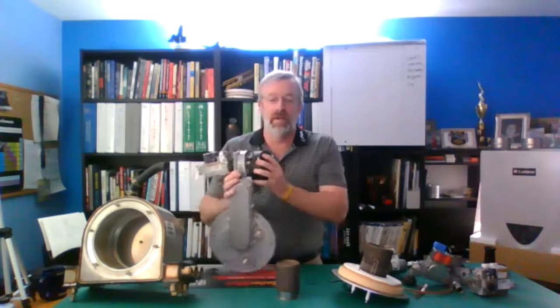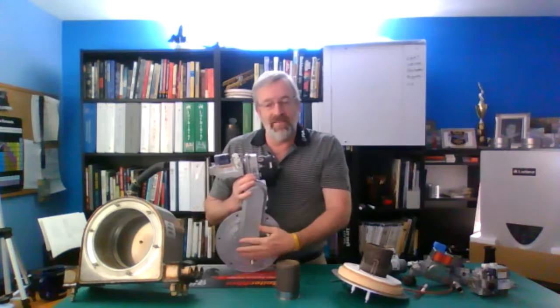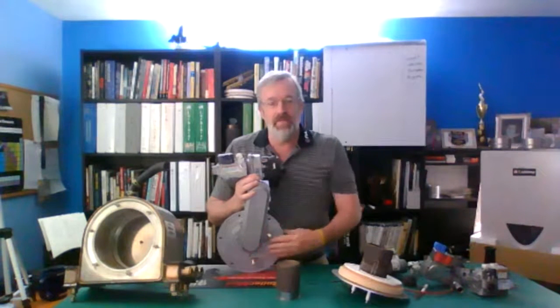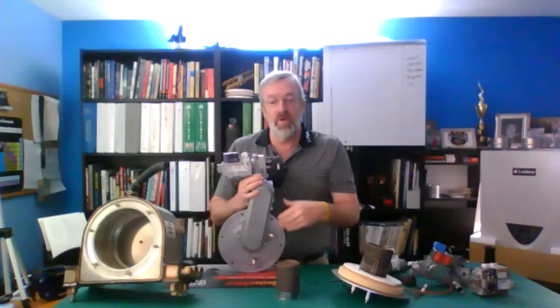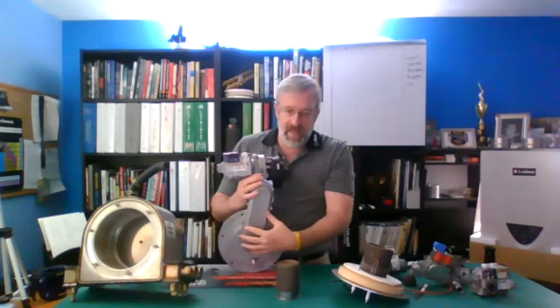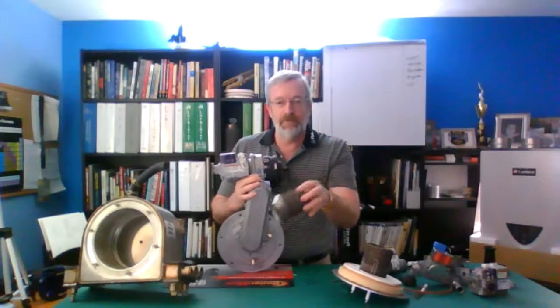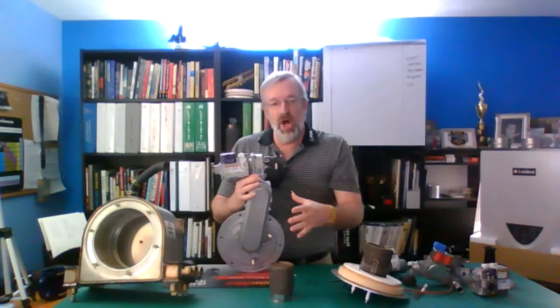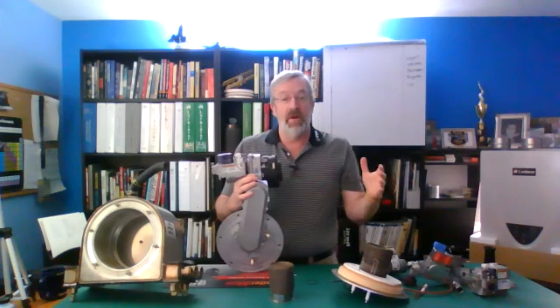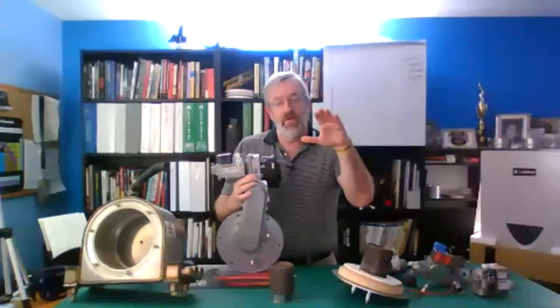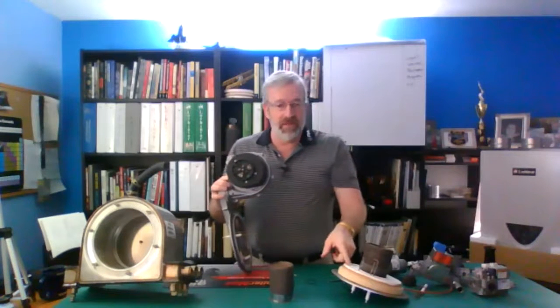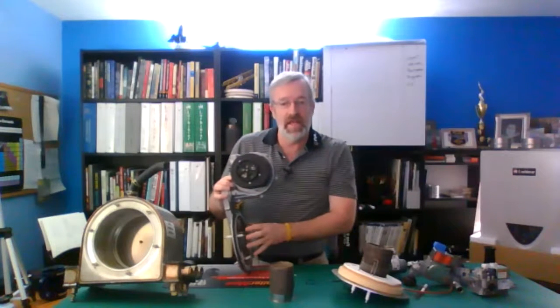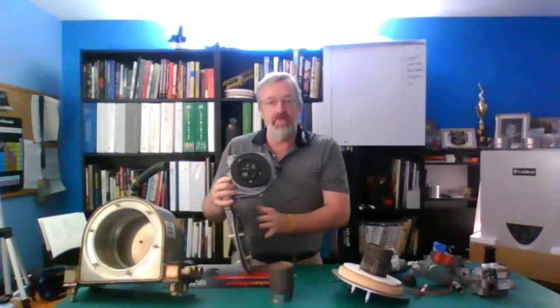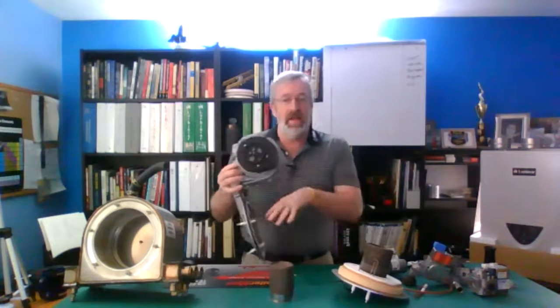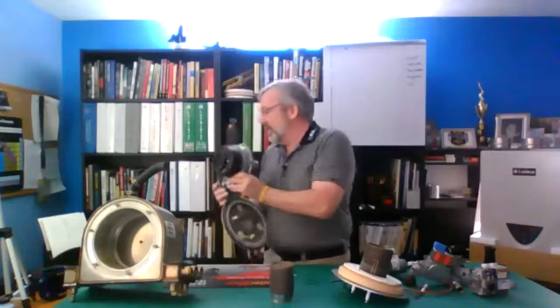Now, real important, don't take this off while this burner assembly, this front door, is still connected. If you take that off, now this is a short one, but when you're into some of the longer ones and you've got maybe a 24-inch burner, the weight of that burner will drop down and basically will crack the refractory, which is the same as this, that's on the inside. So take it all out, set it down where you can work on it, take it apart, remove your burner.